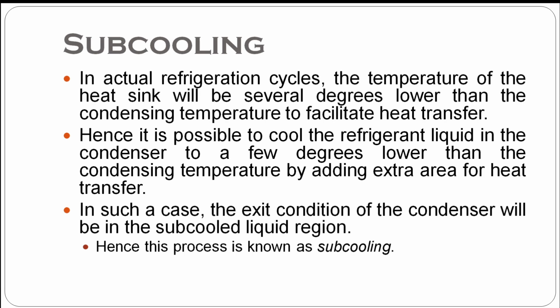And further, for the liquid refrigerant at the exit of the condenser, further cooling is possible, a few degrees lower than the condensing temperature, by adding extra area for heat transfer. You know that the rate of heat transfer is proportional to surface area, right? Heat transfer by convection. So the lowering of the temperature of the liquid refrigerant is possible by adding surface area to the condenser heat exchanger. In such a case, the exit condition of the condenser will be in the subcooled liquid region. That process, lowering the temperature of a liquid refrigerant after condensation, is termed as subcooling.